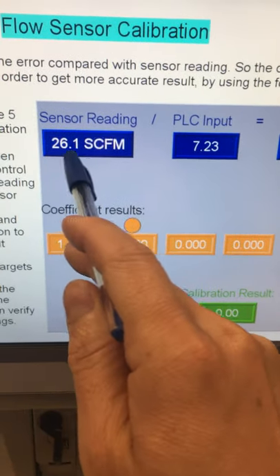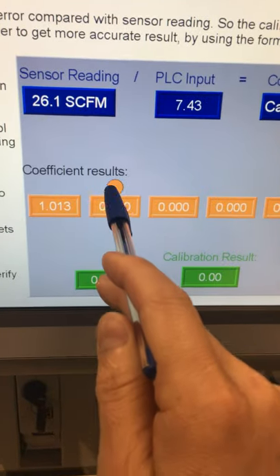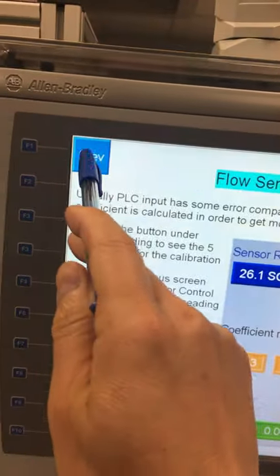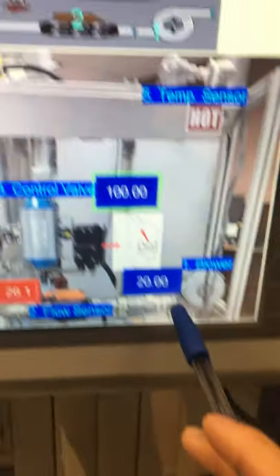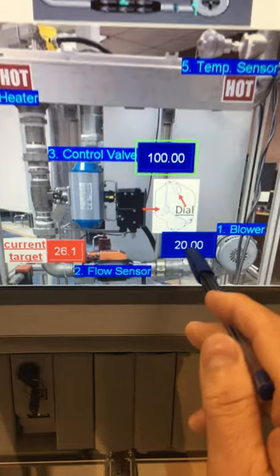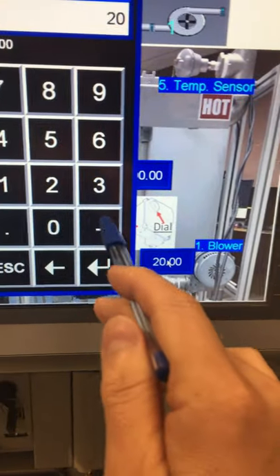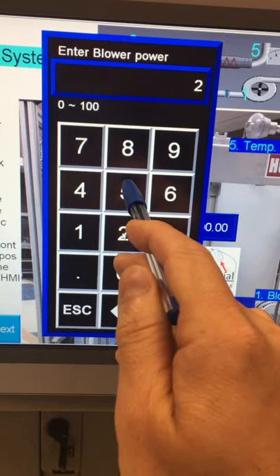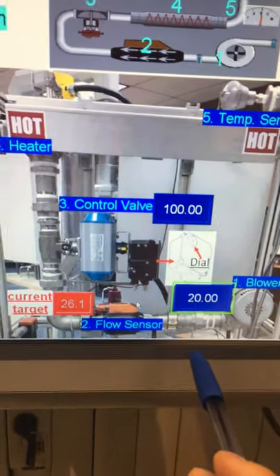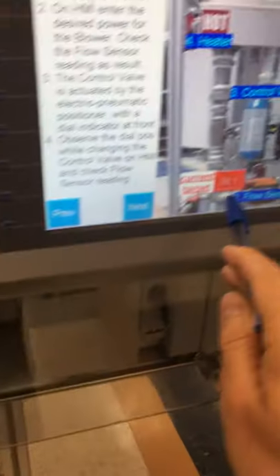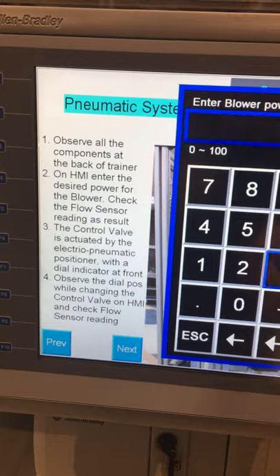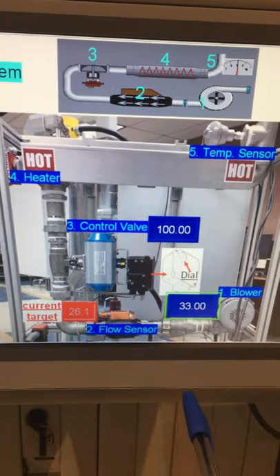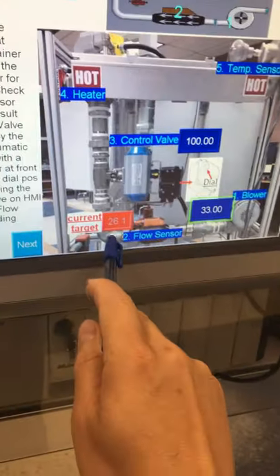For the next target, we need to get 26.1, right? You can see right now it's on here. So we need to go back to the previous screen and change the blower. You can also change the control valve, but I'll just focus on the blower percentage. Right now I need to increase. Probably I need, I don't know, it's just trial and error, right? 27%. Let's see if we can get 26.1. Look at here, it's 15, it's increasing, but not 26. So now we need to increase maybe to 33. Let's try again to see if we can get 26.1.